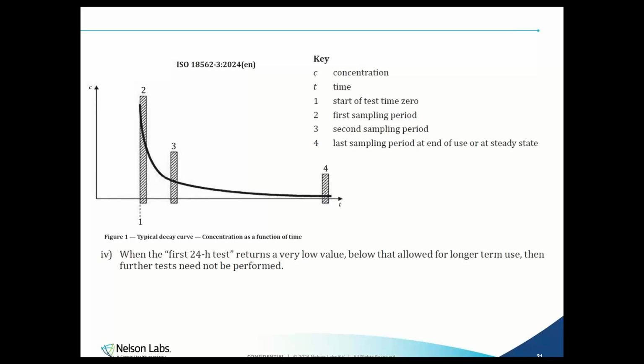It is expected that most VOCs are released as soon as the device is new and taken out of the packaging. I'm sure we have all experienced this as we get something new, open it up, and are hit by all the volatiles coming off. It's almost like that new car smell. It doesn't last. As these medical devices are sampled, we are expecting that exact same thing. More VOCs right away, and then going down over time, or going down over the sampling periods.